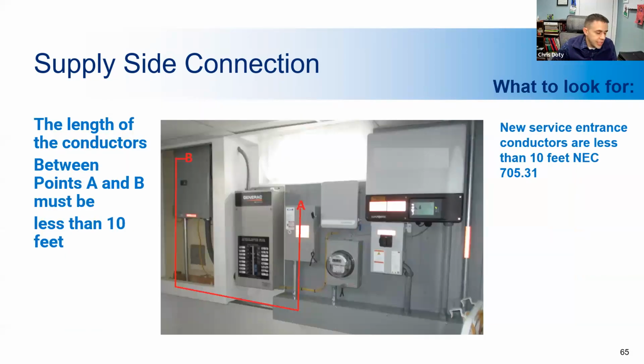In the 2017 NEC, which is what NYSERDA has adopted at this point, it states that the length of the supply side conductors must be no more than 10 feet unless other means are taken to protect them, such as current limiting devices. You can see here the inverter output. It starts at A, and then the connection is at B, the supply side interconnection, and that can be no more than 10 feet.